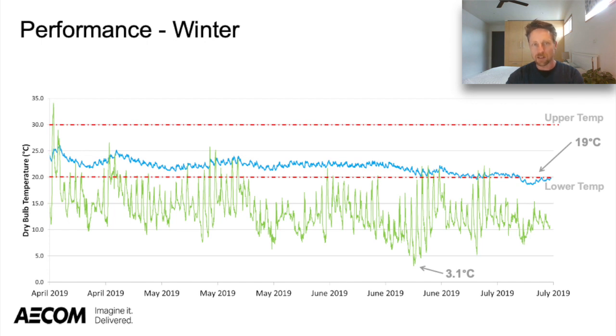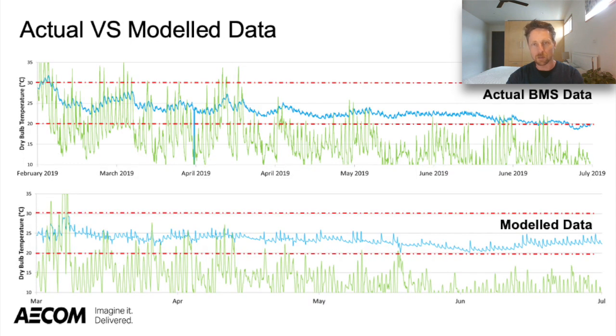Comparing this back to the model data is where we're really happy with the result. We did a lot of modelling work to prove this building would operate well, and compared to actual BMS data, it's amazingly consistent. Where differences exist, they're primarily due to differences in weather files, shown here in green: the actual BMS data reflected significantly hotter summer days, and in winter we had lower occupancy, which wasn't accounted for in the modelling. Overall, a really good result for how the building has performed in response to both summer and winter.